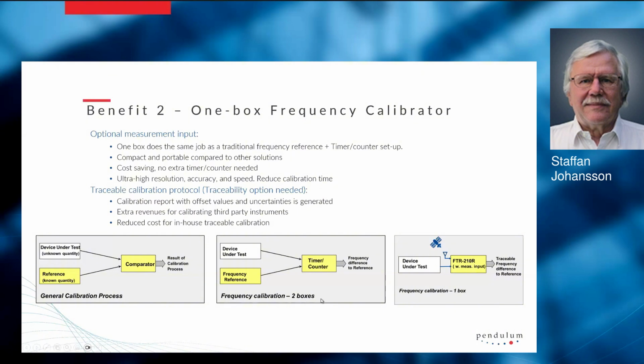Specifically for frequency, you have your frequency reference and you have your device under test, providing two input frequencies to a timer counter that is comparing these two inputs, normally phase comparison, and then you provide output data and you post-process it to get the frequency difference of the device under test to the reference. That requires two boxes, frequency reference and a timer counter.